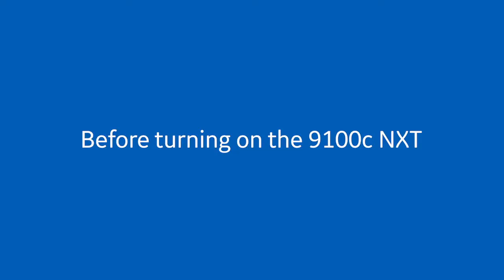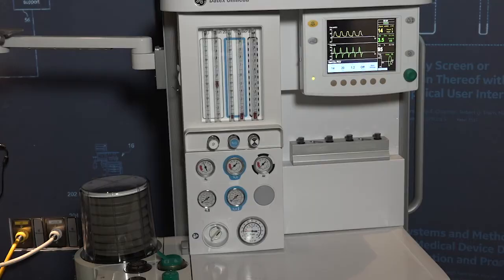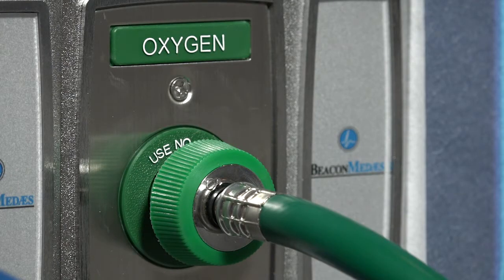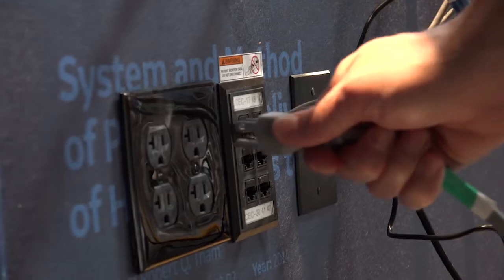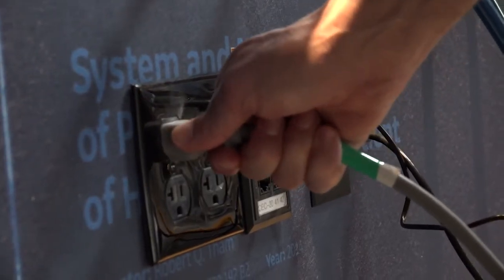I'm Lisa Nolan, global education leader with GE Healthcare. For the 9100C NXT, connect the gas supply hoses to the wall gas source or turn on the gas cylinders. Plug the power cord into an electrical outlet.